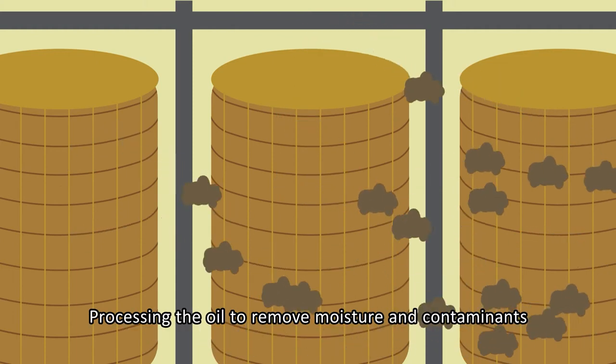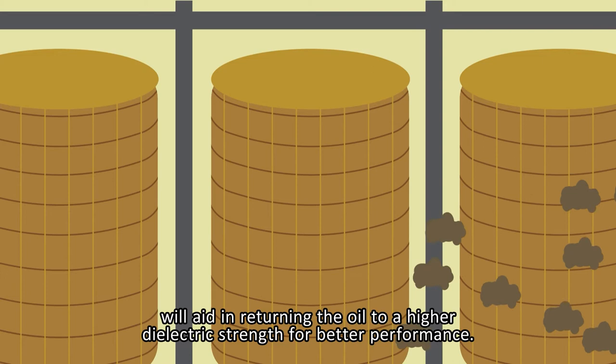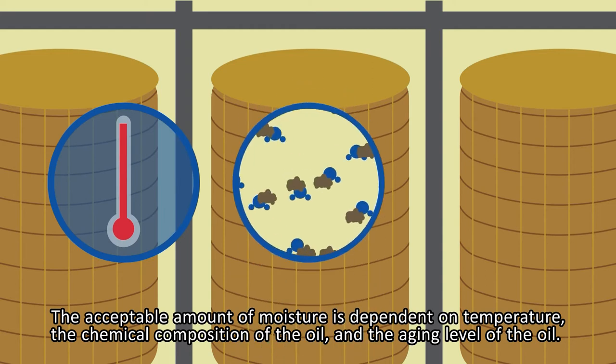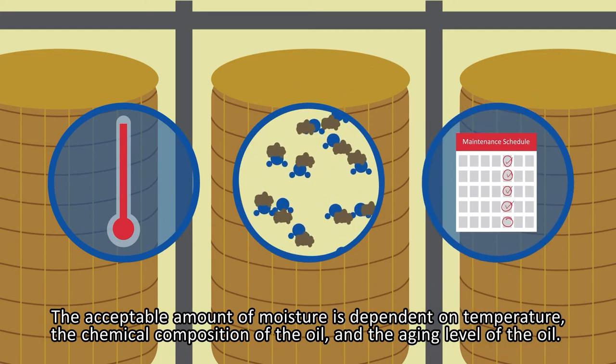Processing the oil to remove moisture and contaminants will aid in returning the oil to a higher dielectric strength for better performance. The acceptable amount of moisture is dependent on temperature, the chemical composition of the oil, and the aging level of the oil.